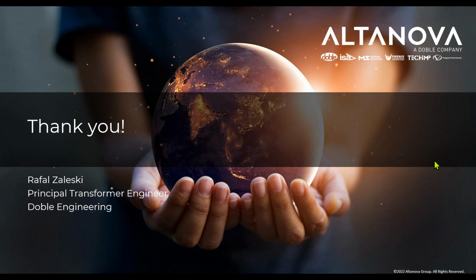Let me read it. Should we test all tap positions? Well, I always say that the more tests you do, the better, or the more often you test a transformer, the better, because it brings you some more information. And then you can draw something from that, but testing all taps is, in my opinion, way over the top. If you follow the IEC standard, it tells you the tap position with all the turns of the regulating winding included, and the tap position with the regulating winding excluded from the test. So this is also my recommendation. It actually came from Doble, that recommendation.